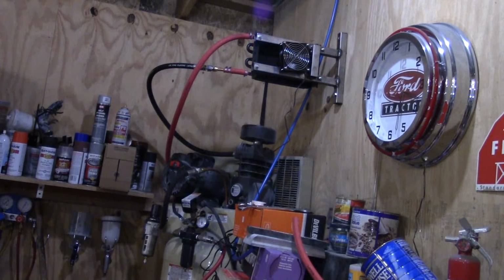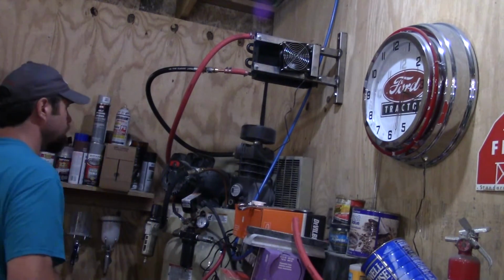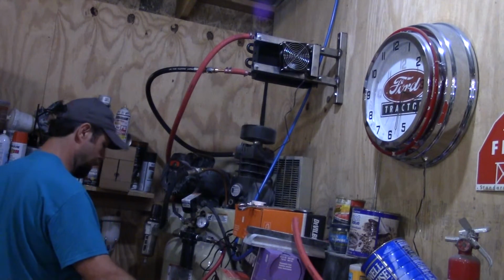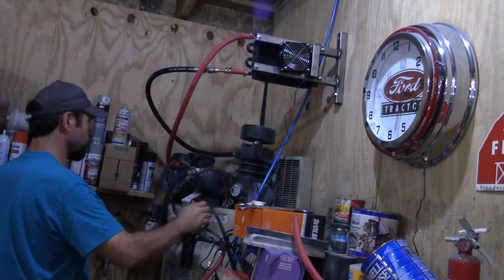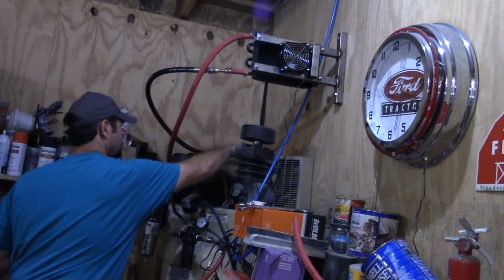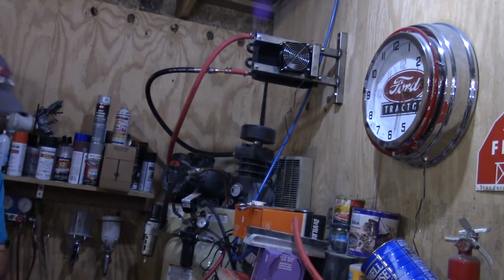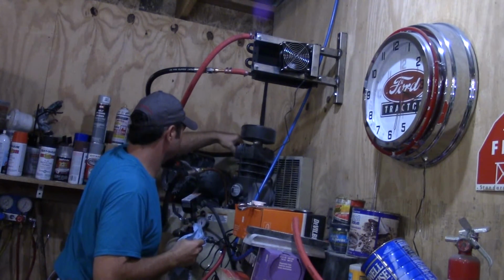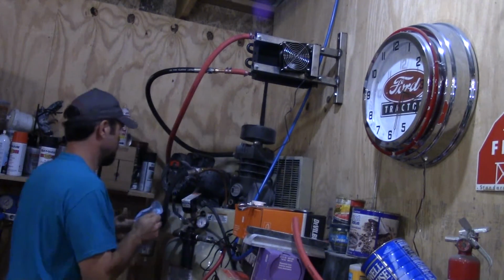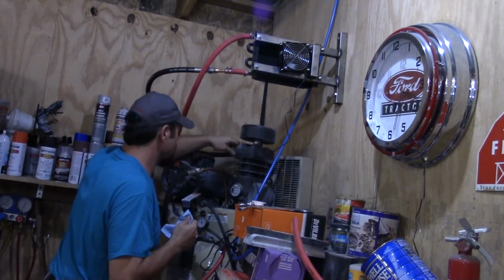I don't know what's going on with this thing. It did that before. It made a hell of a racket. I think it's vibrating. But I killed the breaker on it. It is vibrating. So I moved this thing, and it's actually just walked toward the wall some. So I'm hearing a leak. Why ain't this thing drained down yet? This does drain automatically, but I've got a leak on this fitting.